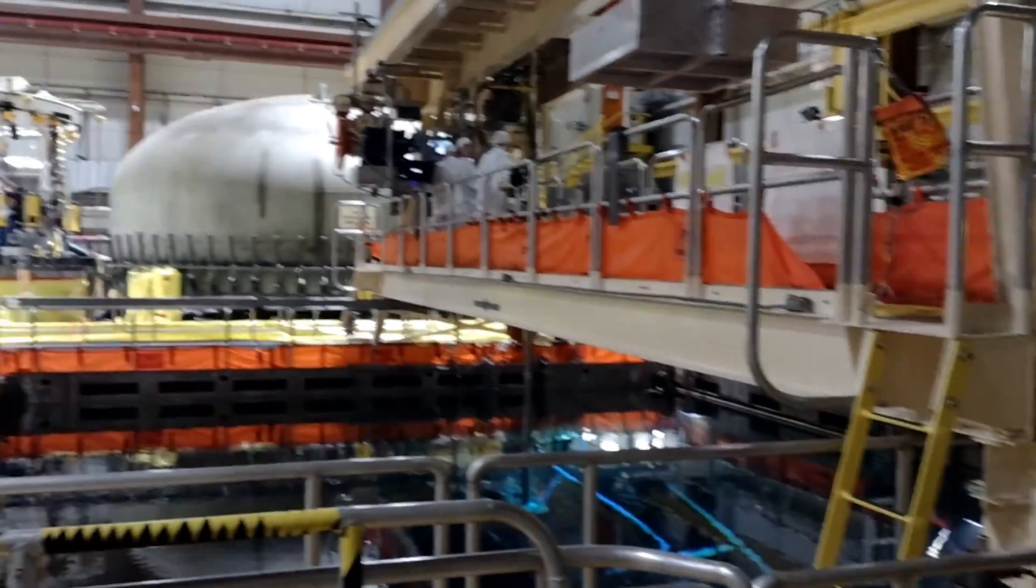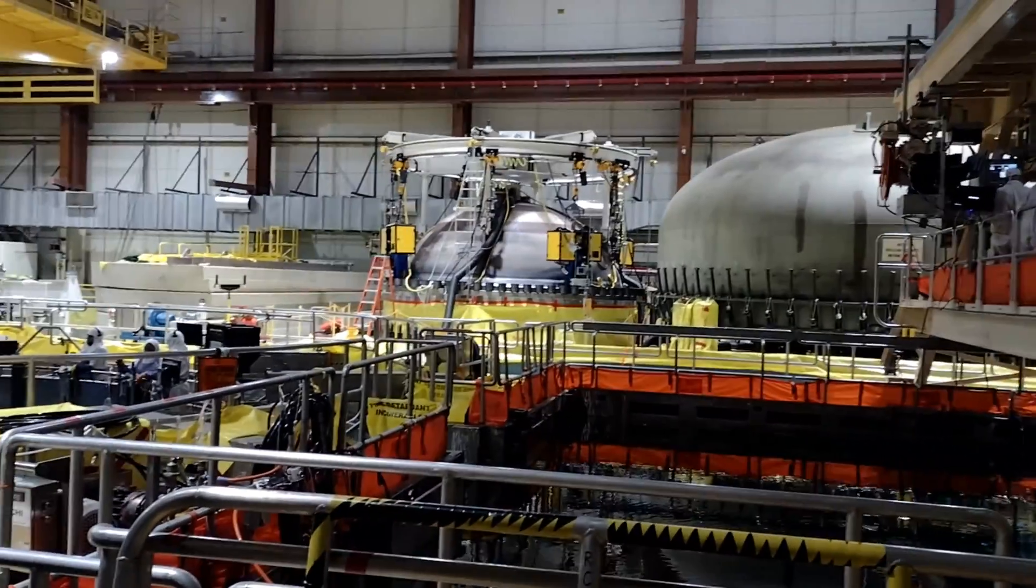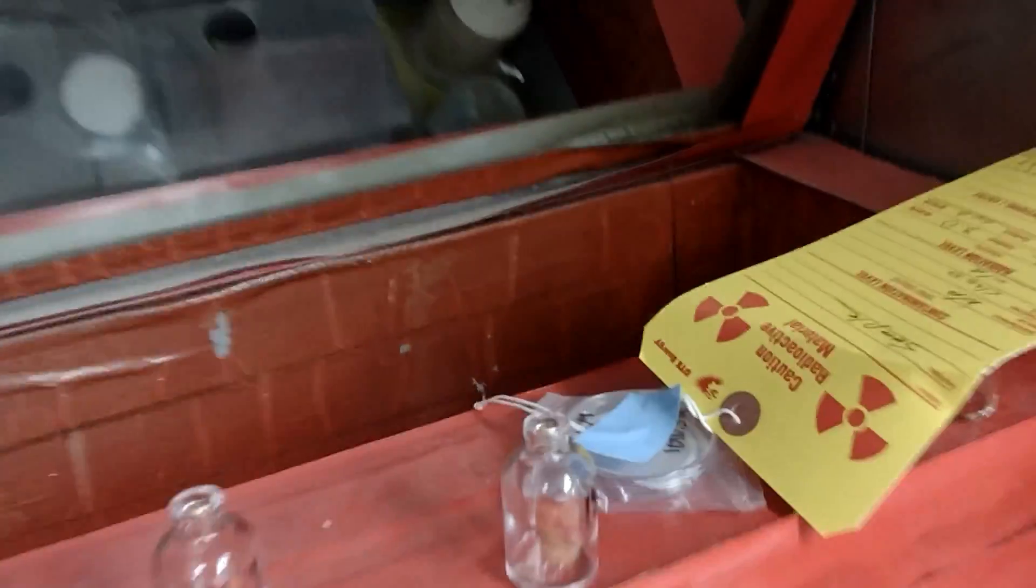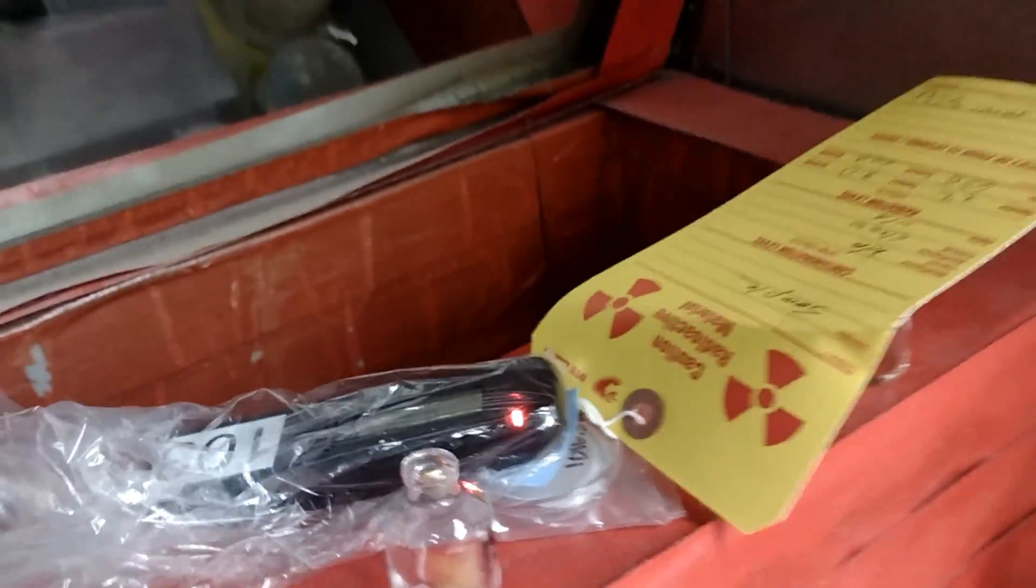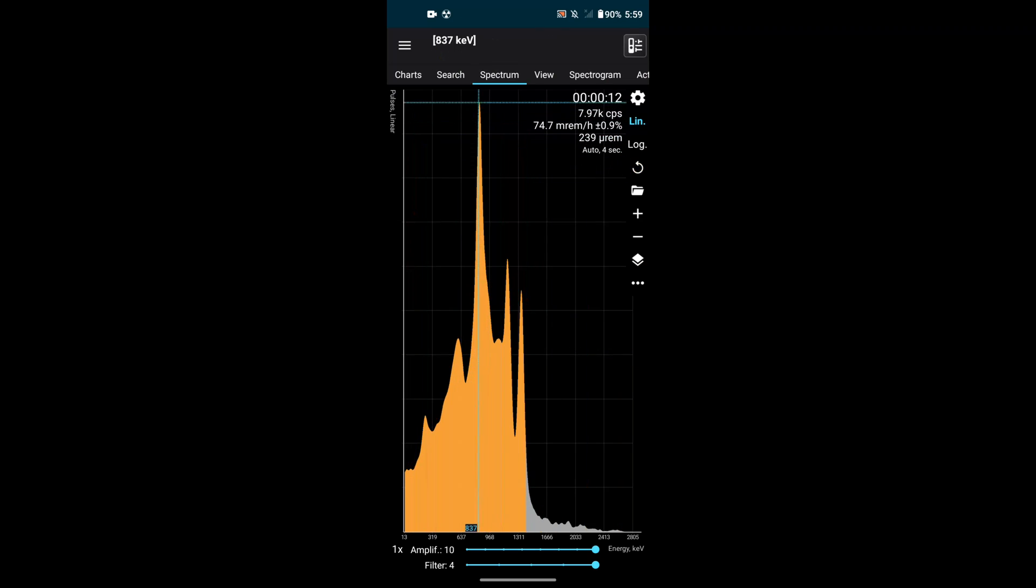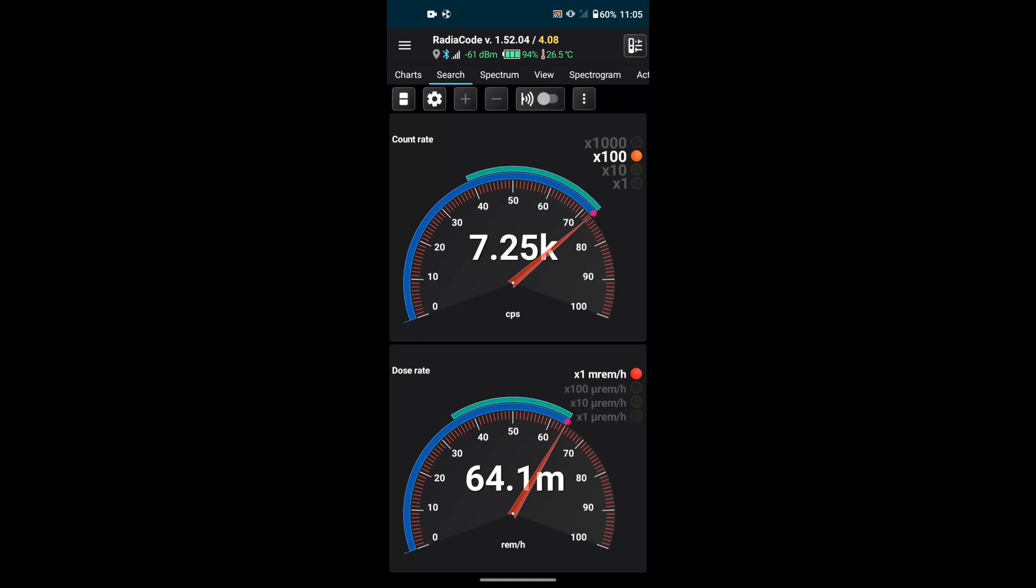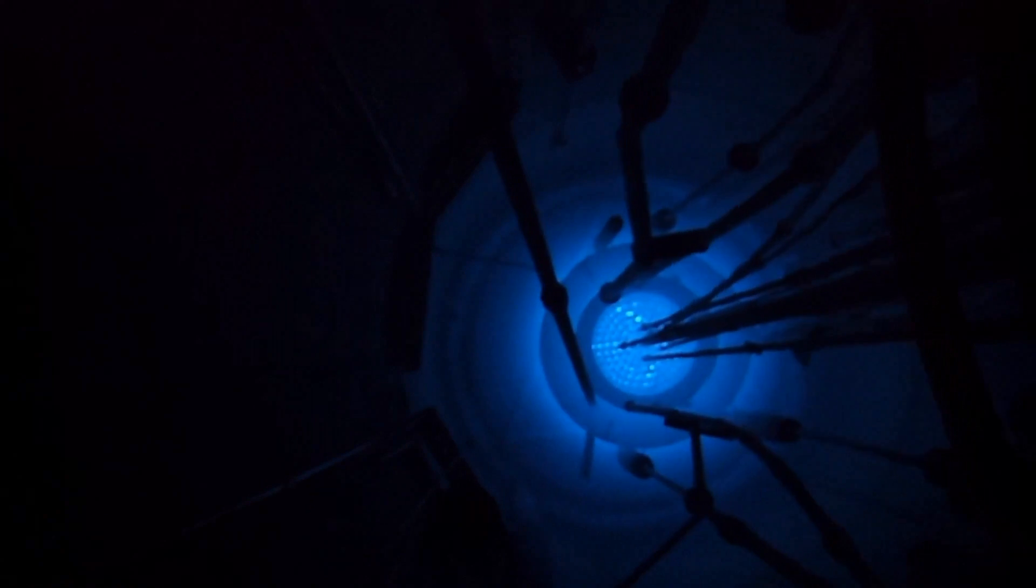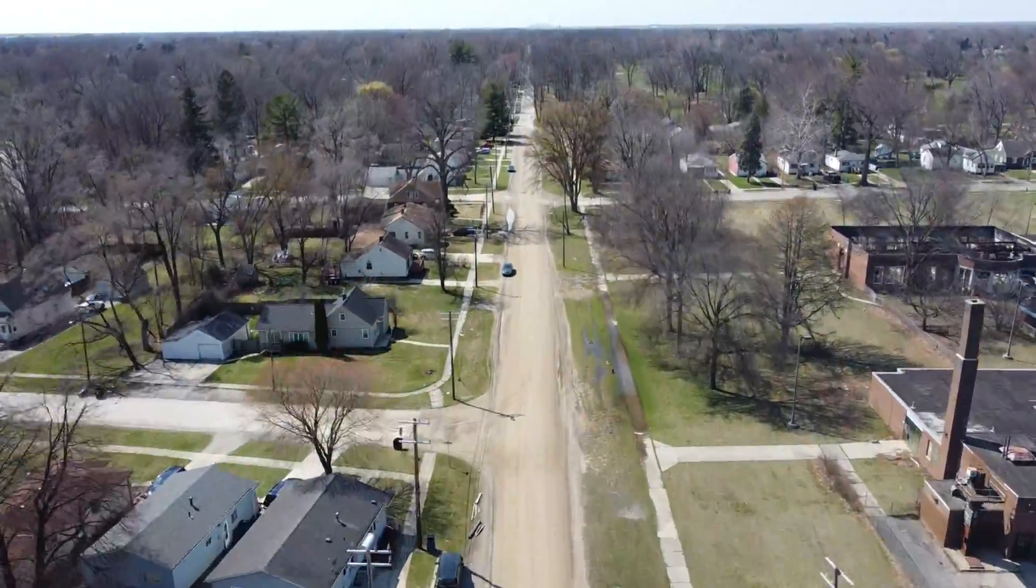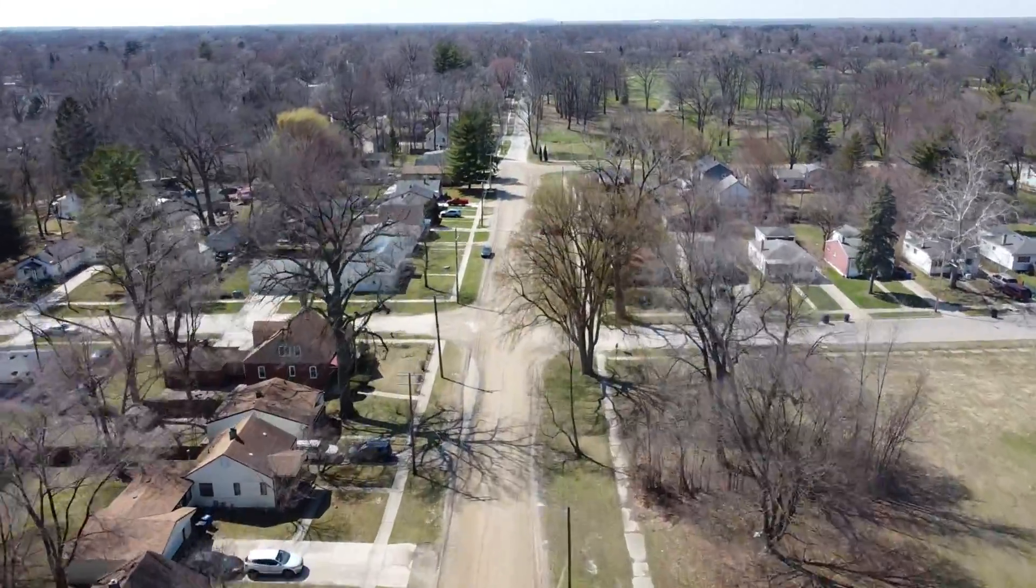This may be a bit much to ask if the company wanted to expand its market. This could be a selling point for the nuclear industry. For example, this source maxed out the meter fairly quickly and this big unidentified peak showed up. Unfortunately, Manganese-54 is not part of the default library of the RadiaCode. Manganese-54 is one of many activation products from neutron capture on iron-rich corrosion product in the core and is not found outside of nuclear reactors. After all, this is a device designed with the general public in mind and low natural radioactivity, but we can fix that.